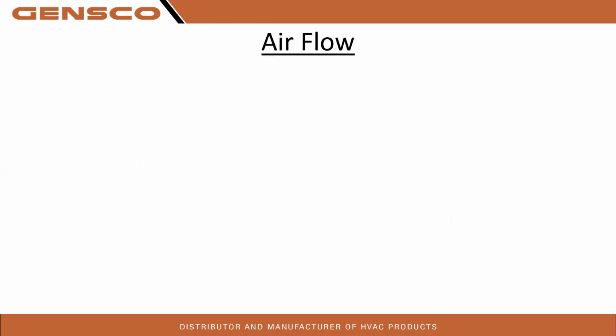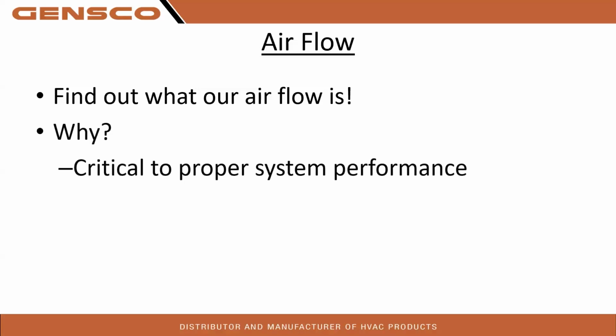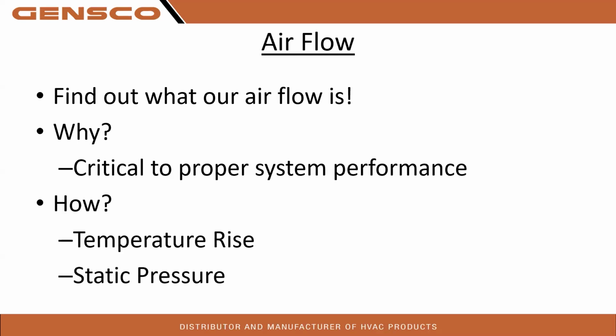So what do we do? Find out what our airflow is. Why is it so important? Because it's critical to proper system performance. Again, I've always used this analogy with all my homeowners. It's worked for 4 years. Why is it failing now? You take a hair dryer and you cover the back of a brand new hair dryer by 50%, so you're only pulling in 50% of that air. It'll still work, right? It'll run, it'll operate, but what's it doing? It's overheating those elements. It's overheating that blower motor. That's a good definition of constant torque. It's constantly trying to work as hard as possible to keep that airflow going over that heat strip, and it will lead to premature failure.